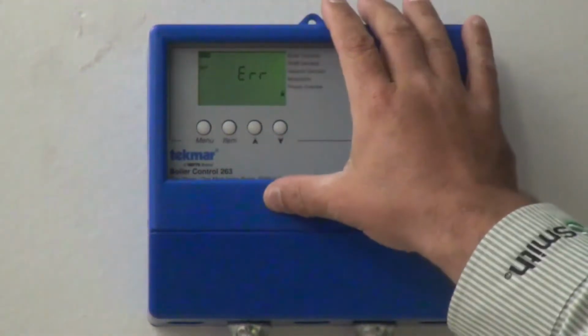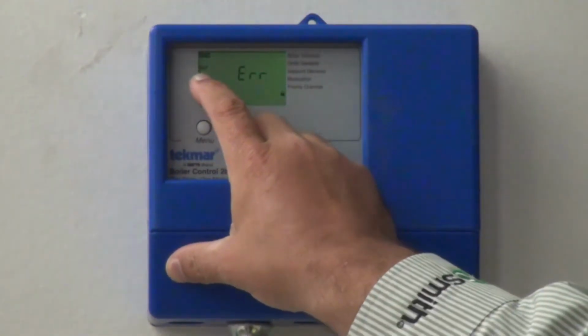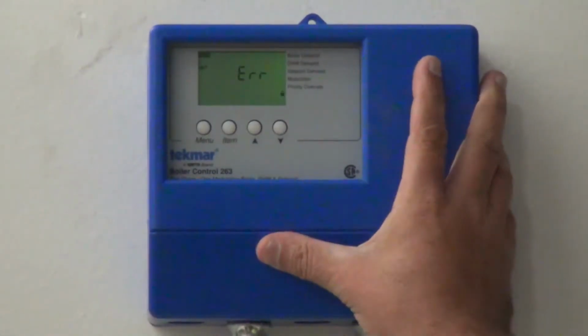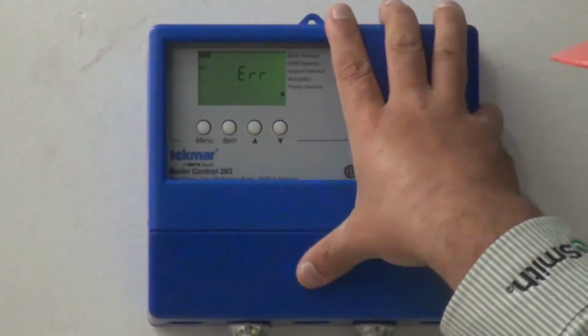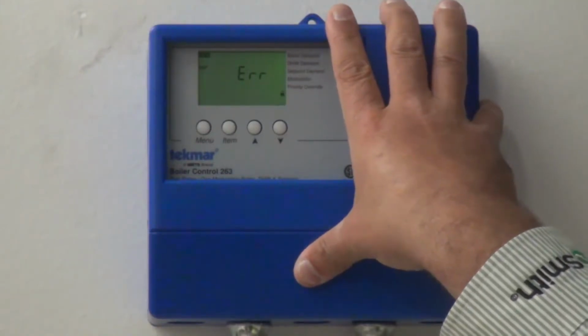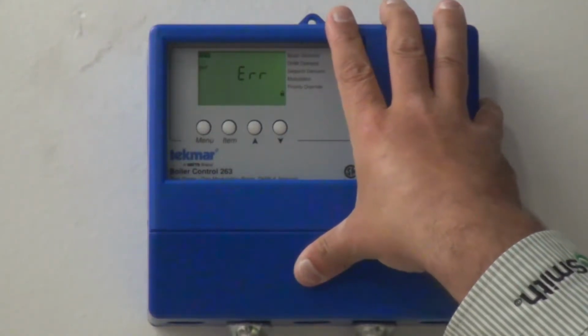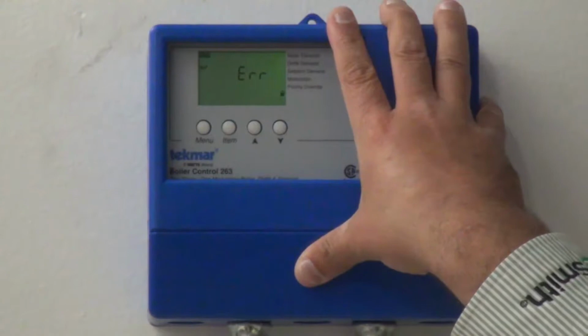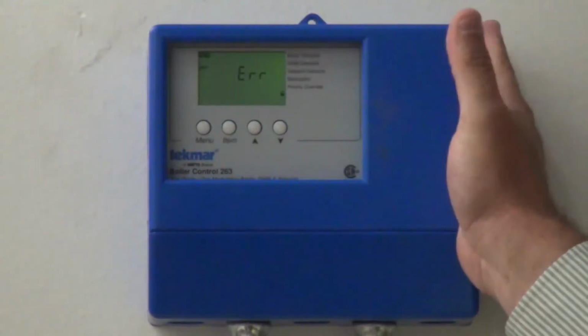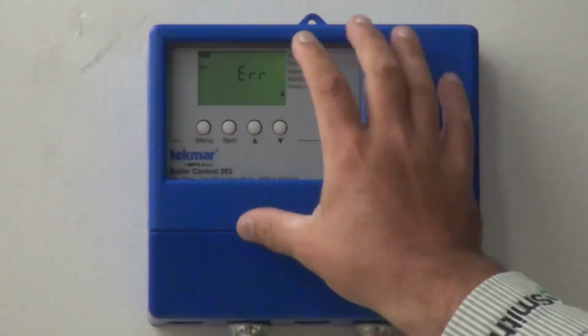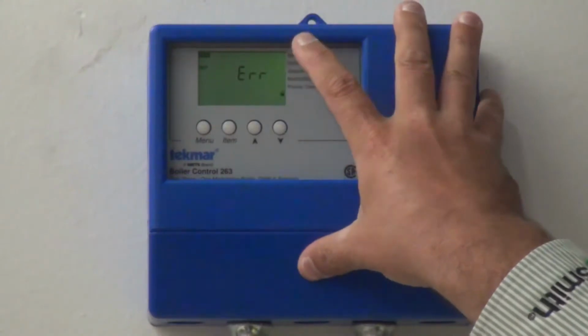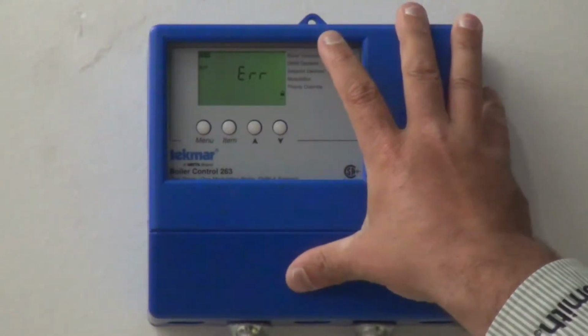So I'm going to go through what I know on this. This is saying an output. You've got a couple of things this controller can do. The one that we're using this for is to modulate these boilers. We're rotating the boilers based on run cycle. But this can do a lot more than that. Sometimes you're going to see some codes on here and wonder why it says air. I'll try to explain to the best of my ability.